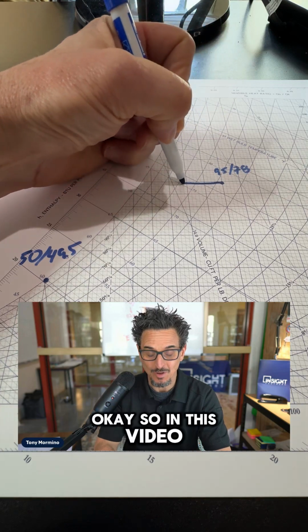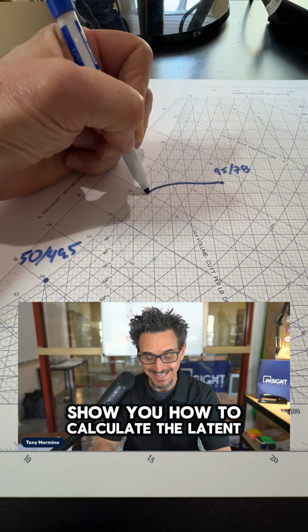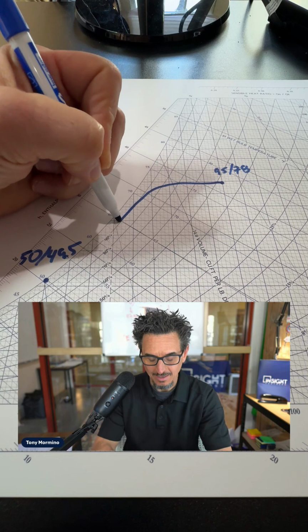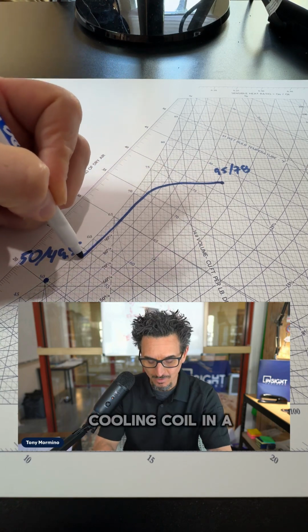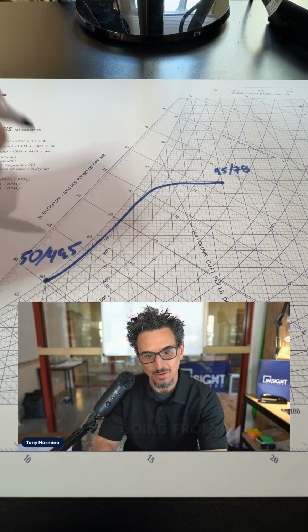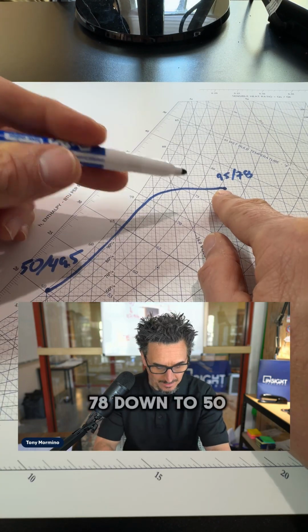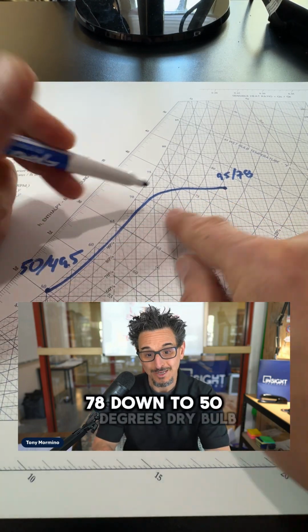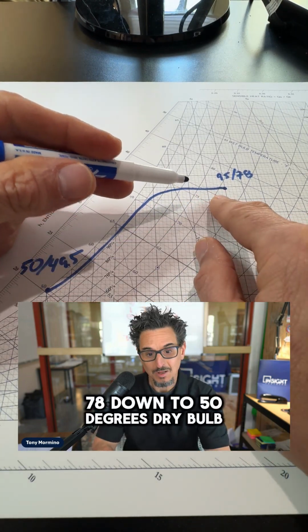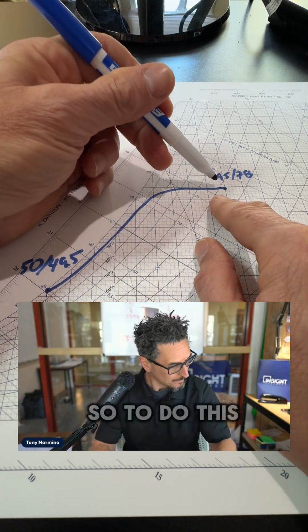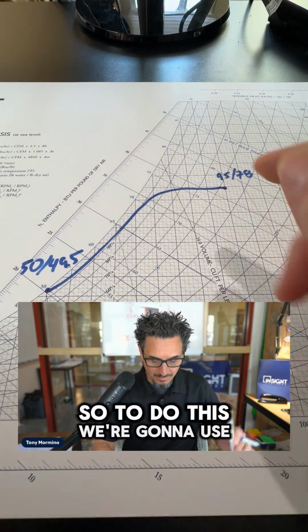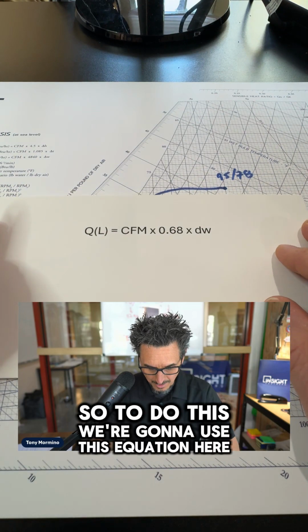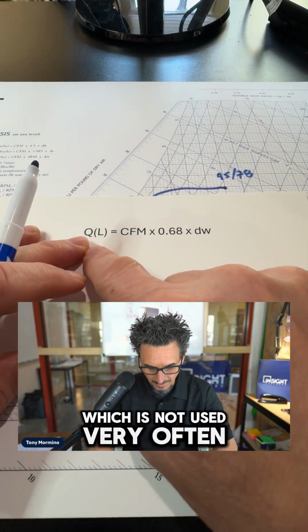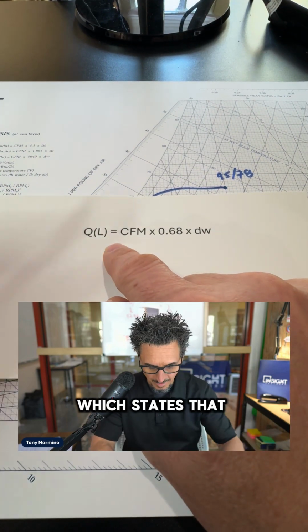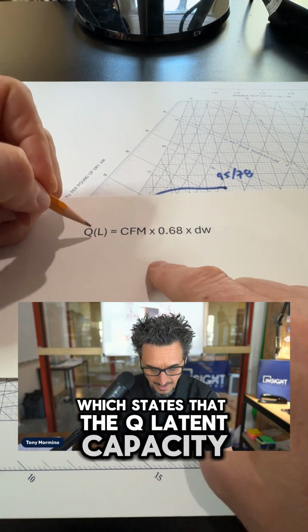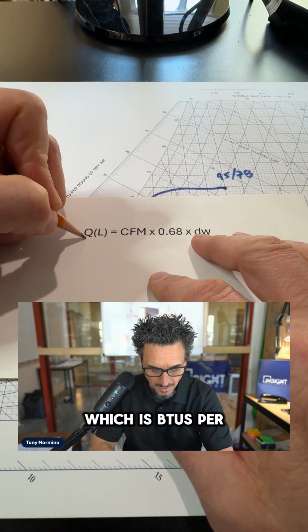Okay, so in this video, I'm going to show you how to calculate the latent cooling capacity of a DX cooling coil in a makeup air unit going from 95, 78 down to 50 degrees dry bulb and 49.5 wet bulb.